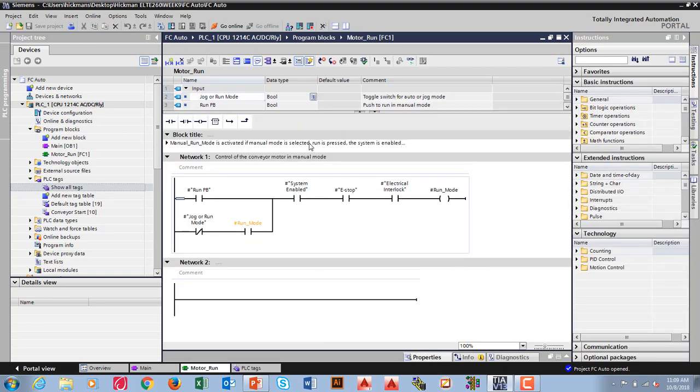Okay. Another couple of things that we had to be concerned about here was the download button, which was right here, Download to Device. Remember, when it downloaded to device, it established communications, and then it often asked you to do something. A lot of times it would be stop all, until you would click stop all and finally get the load. You could do that, and then you would go on. It would go online. If it didn't go online, you could click the eyeglasses right here, and that would be the monitoring of this while it's online.